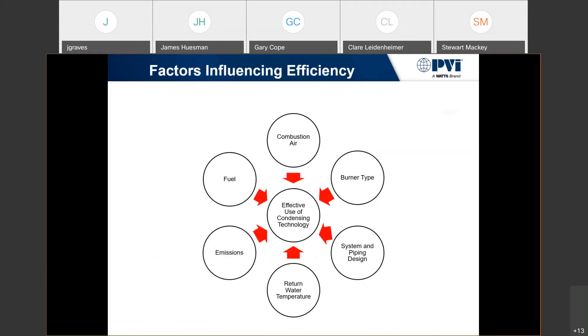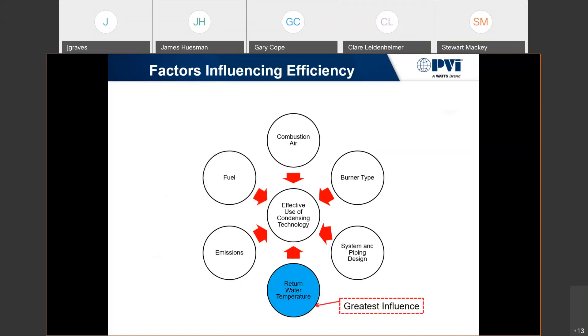There are a bunch of different factors that influence the efficiency test: the fuel, type of burner, quality of burn — which is a mixture of combustion air and emissions — and also your return water temperature and piping design. The main factor with the most influence is your return water temperature. The higher the temperature of water we're feeding it, the fewer BTUs we can put into the water to hit the target of 140.